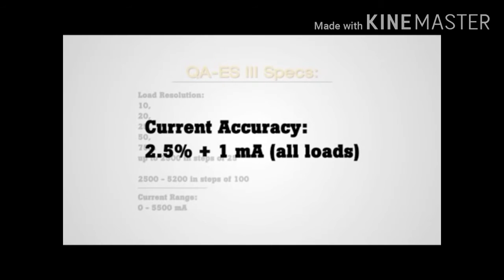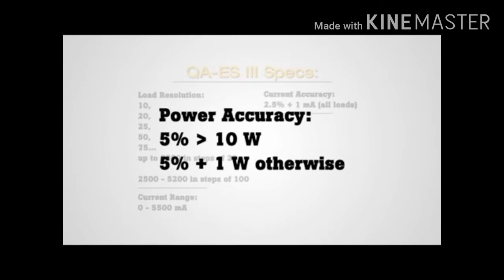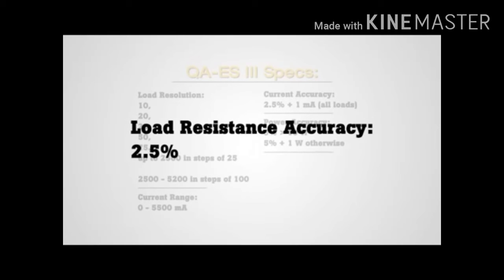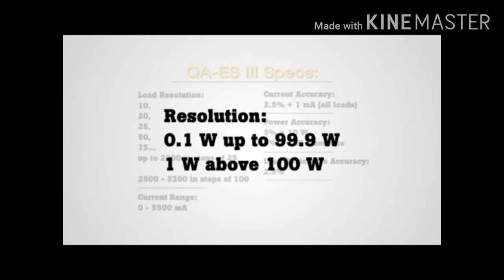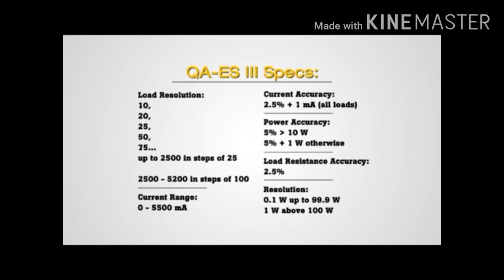Plus, it's twice as accurate with current accuracy, 2.5% of reading, plus 1 milliamp for all loads. It's exceptionally accurate with generator output power accuracy of 5% greater than 10 watts and 5% plus 1 watt otherwise. In addition, it provides a load resistance accuracy of 2.5%. The QA-ES3 is also highly precise with a 1/10 of a watt resolution up to 99.9 watts and 1 watt above 100 watts for power measurement.